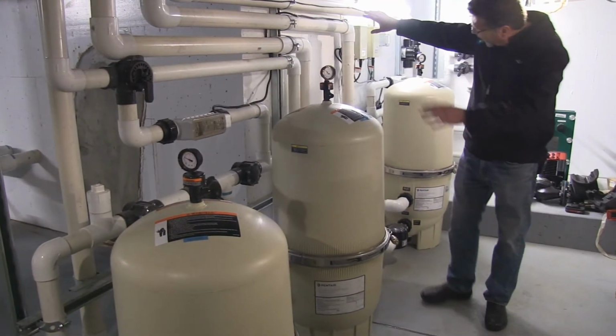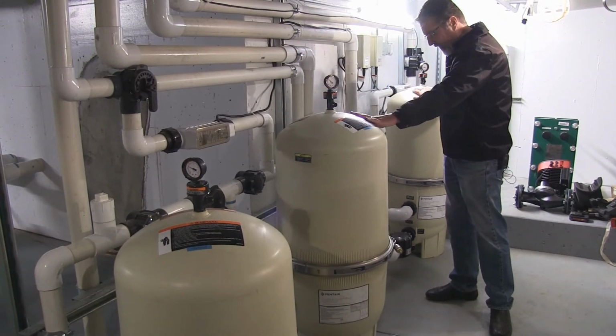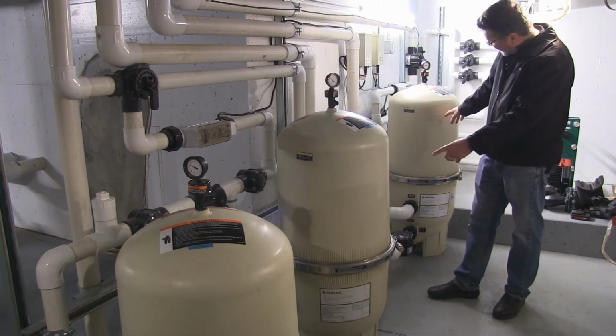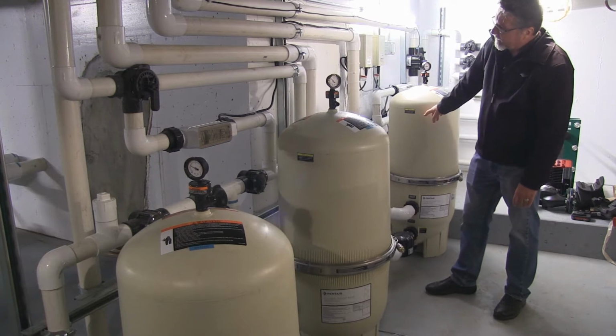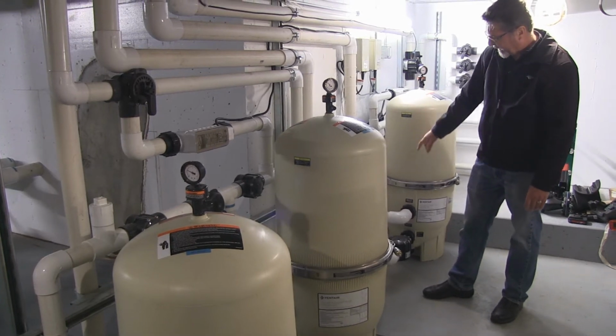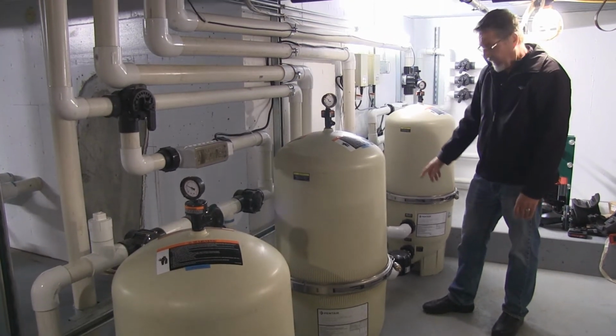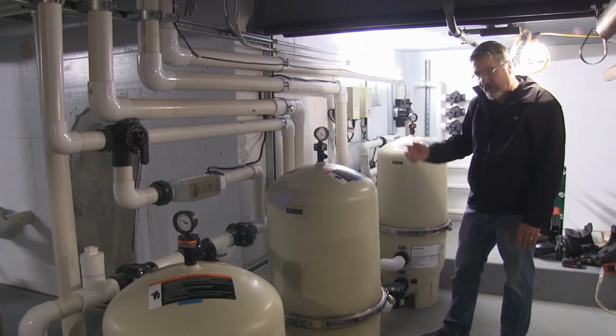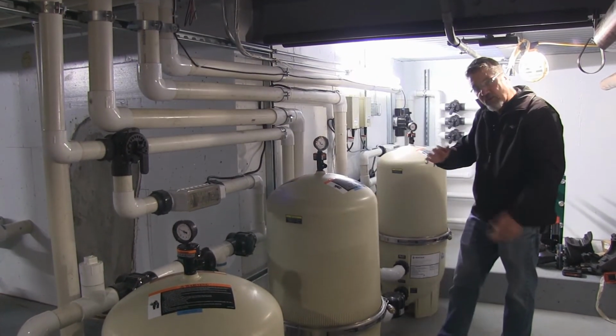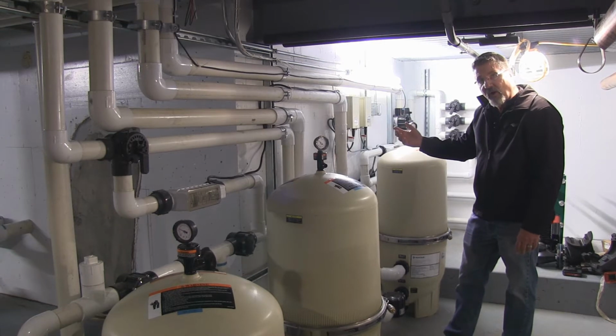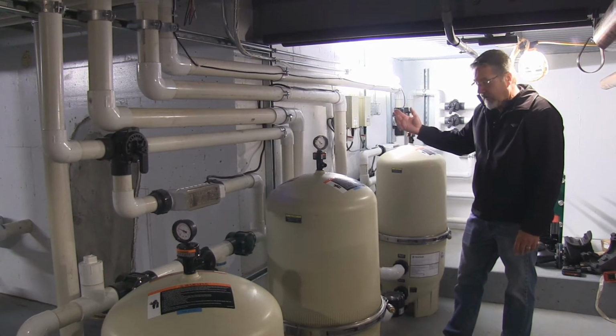Here we come in from both of our pumps for the pool. They go in individually—again we're running in series here, and we don't go in parallel again until after these are filtered, with check valves so we can isolate. Again, we can run one system, open up a filter on one pump if needed, and still draw all the water from the entire system.